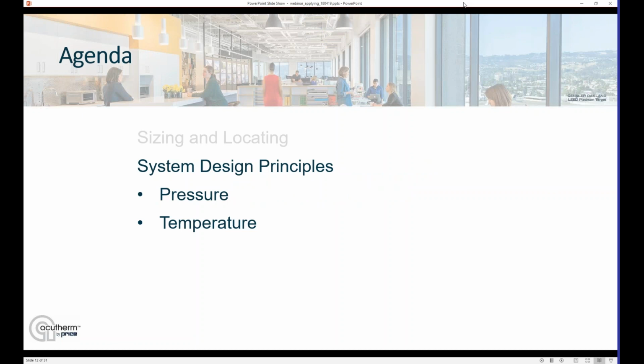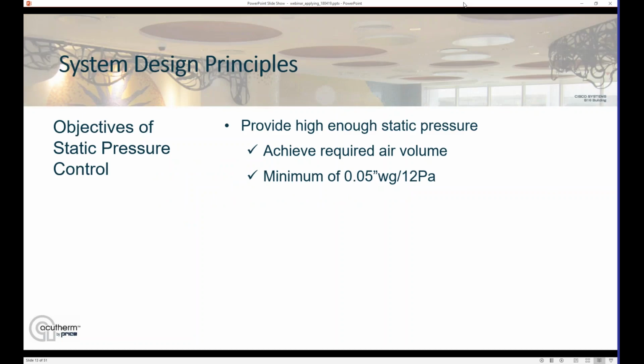System design principles, our next topic. Really two key things to make sure your Therma-Fuser diffuser system works well, and that's taking a look at the pressure and the temperature within the system. So objectives of pressure control. Really, you need to provide enough pressure to achieve the required air volumes in the spaces. The diffuser itself will operate at pressures as low as 0.05 inches water gauge or 12 pascals, but you want to typically go a little bit higher than that because you're trying to achieve some kind of a design air volume in the space. So you want high enough static pressure to achieve your design air volumes, but you want to limit the static pressure.